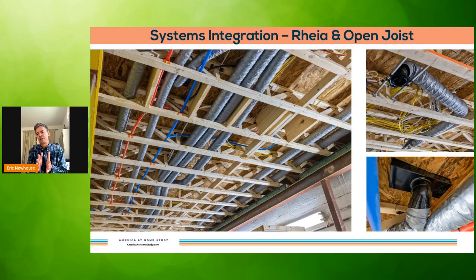Because of the airtight, snap-together connection of the fittings, we were able to implement this approach in the modular environment, with ductwork installed in the first floor, second floor, and third floor boxes at the factory, and then on site we're able to snap them together from floor to floor. The images show how the ductwork is incorporated and installed within the openings of the open web floor truss systems.